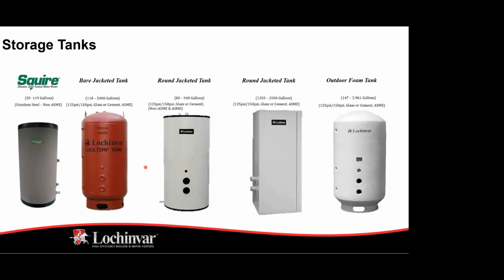Storage tanks. You're going to see some options for non-code. Remember, 120 gallons or greater tends to be ASME. So you've got options for some non-code storage tanks, typically for residential applications. Anytime we're dealing with a commercial building, though, we tend to be looking at ASME just because we have larger storage requirements there. If you're looking at a bare tank, that simply means the external is bare. Internal to the tank, it's usually glass or cement lined.